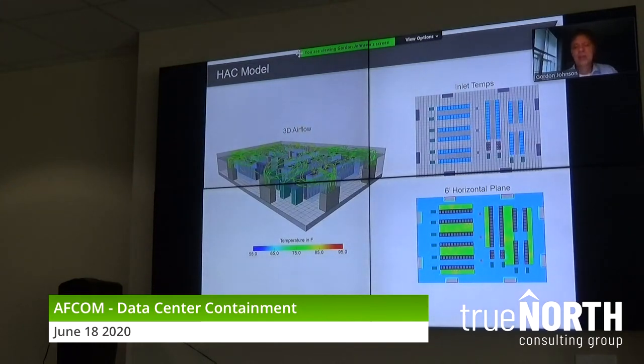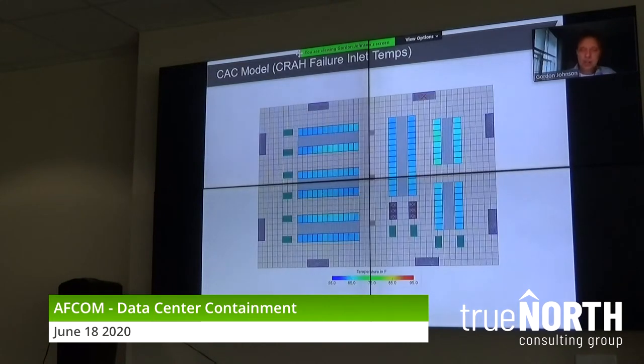where I go. Look at the horizontal temperature plane. Remember that definition of hot aisle containment? I contain my hot aisles, so the rest of the data center now is one big cold aisle. But again, from a thermodynamic standpoint, both data centers have the same inlet temperatures. And that's all, really, when we look at a data center, that's all we care about: what is the temperature we're providing to the inlet fans on our IT equipment? Same data center, we've got cold aisle containment.